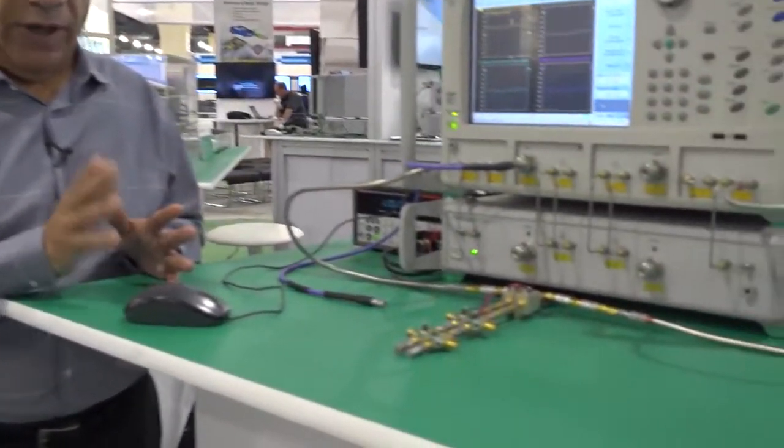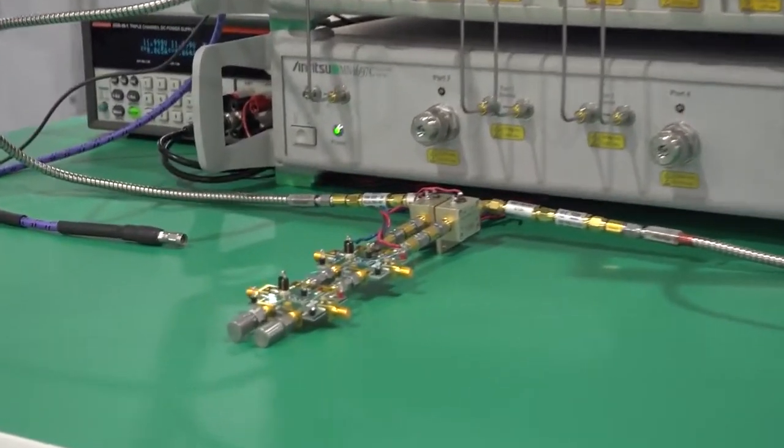So the typical situation for a cold source method is to terminate the DUT and measure the noise power of the DUT. In order to do that, you must first characterize the system. So we do that by first measuring the DUT, getting an SNP file, and then storing that for later use. We then analyze the receiver path that the DUT is going to be connected into.